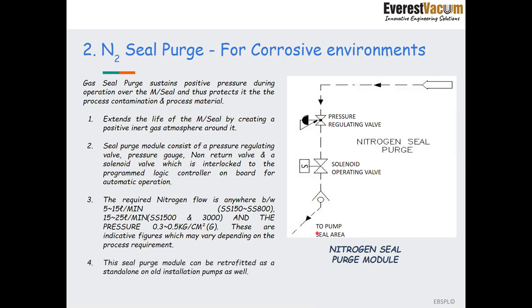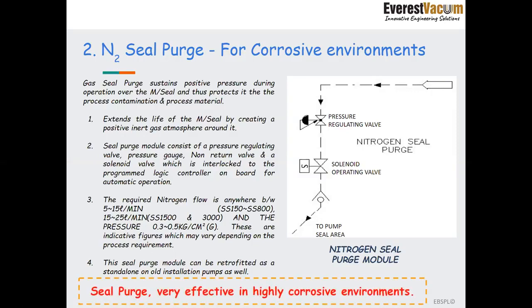And another feature for this module is that this can be retrofitted as a standalone on the old installed pumps available at the site also. Because it is very much possible that certain modules might have been damaged after certain years of running. So this seal purge module can be retrofitted as a standalone unit in those older supplies as well. So seal purge is very effective in highly corrosive atmospheres.